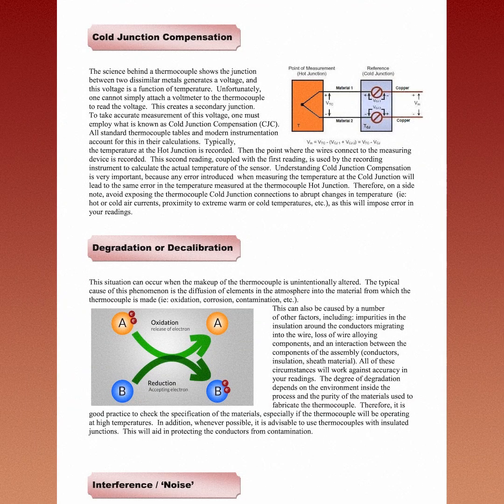Cold junction compensation. The science behind a thermocouple shows the junction between two dissimilar metals generates a voltage, and this voltage is a function of temperature. Unfortunately, one cannot simply attach a voltmeter to the thermocouple to read the voltage. This creates a secondary junction. To take accurate measurement of this voltage, one must employ what is known as cold junction compensation, or CJC. All standard thermocouple tables and modern instrumentation account for this in their calculations. Typically, the temperature at the hot junction is recorded. Then the point where the wires connect to the measuring device is recorded. This second reading, coupled with the first reading, is used by the recording instrument to calculate the actual temperature of the sensor.